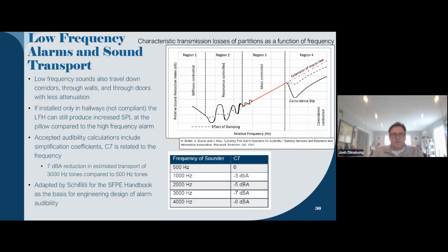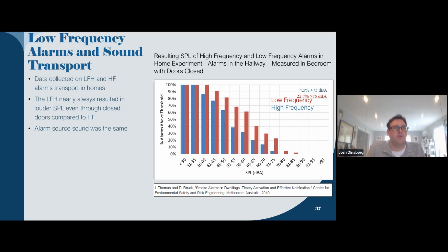So when we're doing our engineering calculations, and this has even made its way into the SFPE handbook for almost 40 years now, we actually apply a frequency effect when we're calculating the transport of sound. That's this constant C7, where at a 500 hertz tone, we don't apply any attenuation or reduced effect, but there's a 7 dBA reduction for 3000 hertz tones. So we already know that sound is going to travel better, even if alarms are installed outside in hallways and not in the bedrooms. This low frequency tone will travel better through your home.